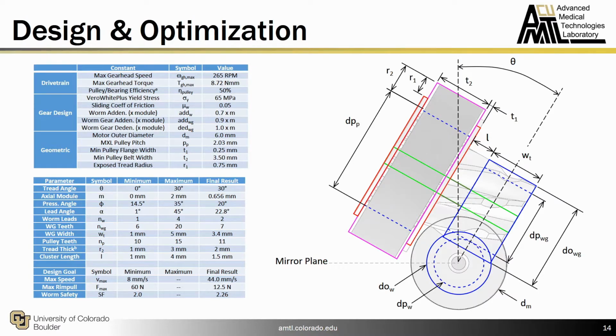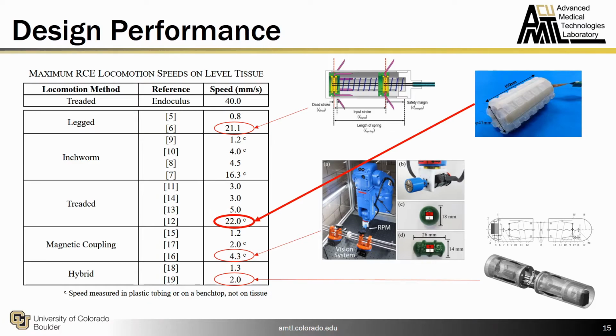only 30 mm by 23 mm, while still meeting all design constraints such as a 2x safety factor for gear bending stress. This design also allowed for speeds above 40 mm per second, almost twice as fast as the fastest recorded robotic capsule endoscopes in research. Additionally, it's important to note that none of these RCEs listed here have the interventional capabilities that the Endoculus does.